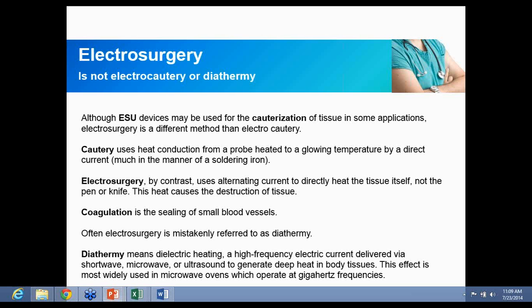Some of that excitation is through the tissue's impedance and the resistance to the current flow, and resistance produces heat. But the majority of this heat stems from rapid vibration of molecules, particularly the water molecule, the H2O molecule. They oscillate back and forth. That back and forth oscillation causes heat. That oscillation is caused by the changing electromagnetic field.